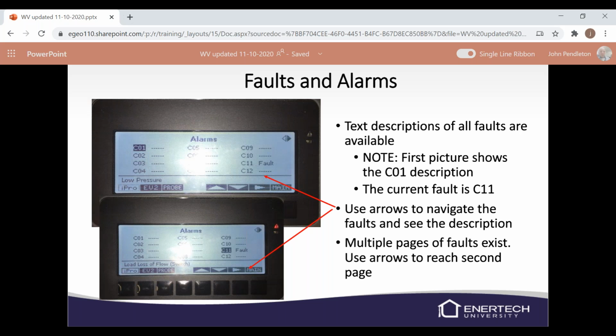You could have multiple faults. A lot of times when we see a C11 fault, we'll see, I think it's a C10, which is a load loss of flow feedback. So sometimes you'll have 2 that really kind of go along together, but you could have 2 faults. Once you get to the C11 fault, you can actually go over and it'll explain a little bit about that current fault. The C faults or the iPro faults, I think there's like 22 of those. So there's a couple different screens. So you have to scroll through different screens to get to the fault.